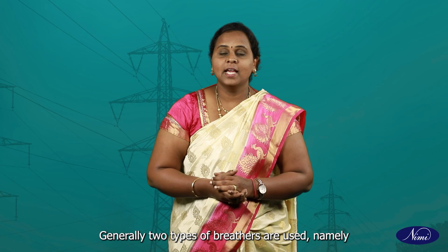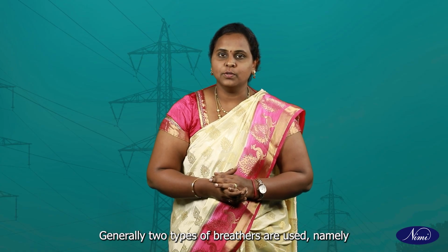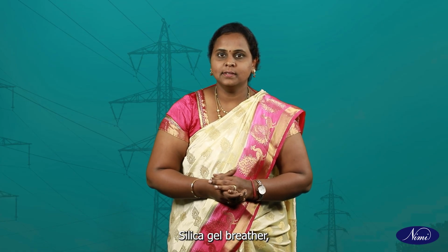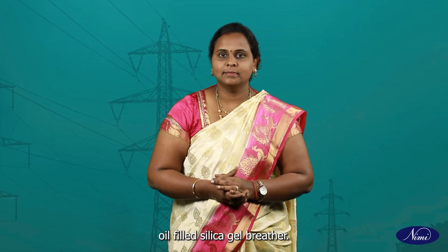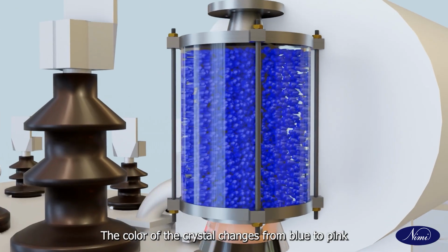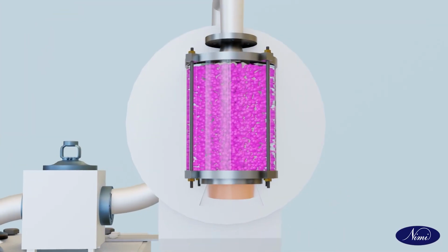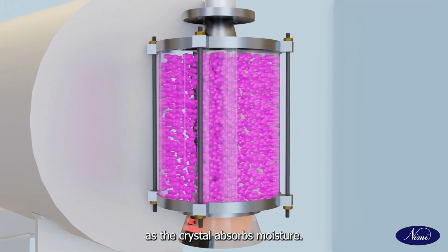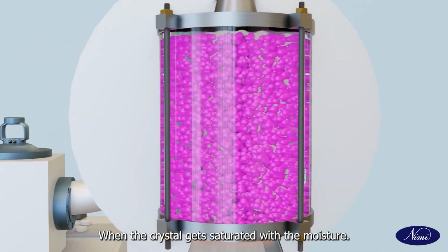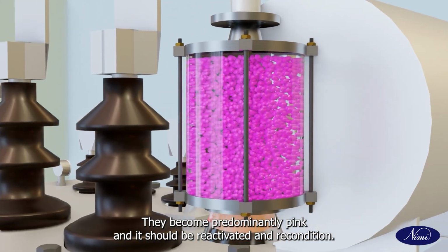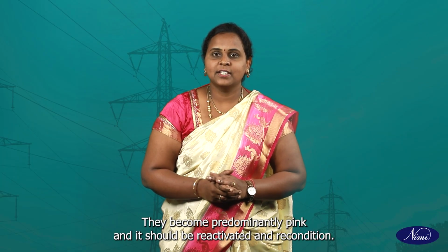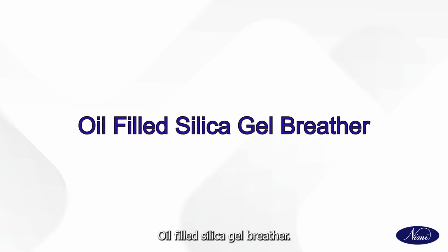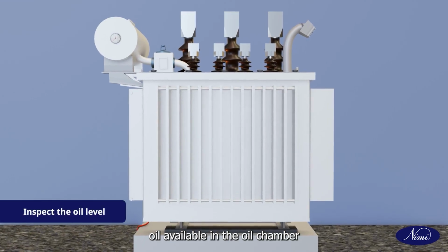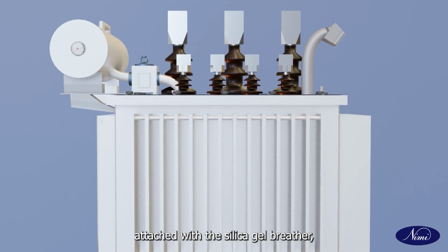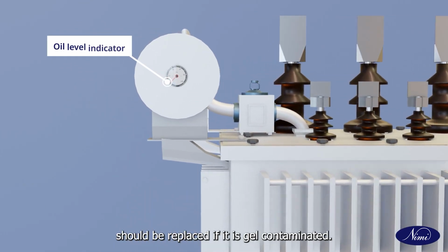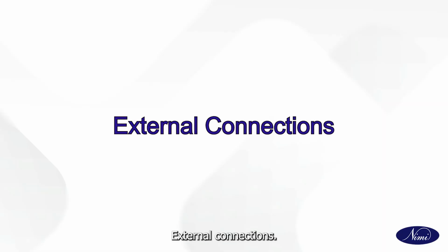Types of breathers. Generally, two types of breathers are used, namely silica gel breather and oil-filled silica gel breather. Silica gel breather. The color of the crystal changes from blue to pink as the crystal absorbs moisture. When the crystal gets saturated with moisture, it becomes predominantly pink and it should be reactivated and reconditioned. Oil-filled silica gel breather. Oil available in the oil chamber attached to the silica gel breather should be replaced if it is contaminated.